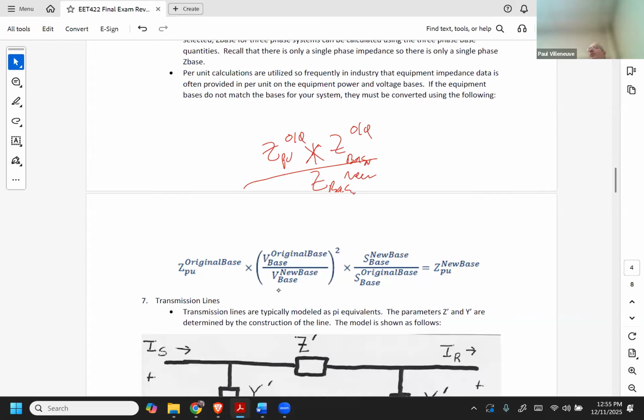It cleans it up a little bit—it collects the voltages, squares them, and does it that way. So if you don't like remembering this or aren't sure where it comes from, just go back: convert from per unit to actual ohms on the original system base, then divide by the new per unit base to get everything into the new per unit system. That's all it is—really just the concept of per unit, put more succinctly.